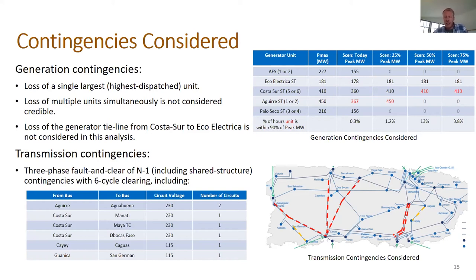All of the contingencies, or actually a subset of the contingencies that we looked at, are summarized in the table on the right, where for each scenario shown in columns going across, you can see the largest conventional units online and what their dispatch was at the time, with the text in red being the megawatt level of dispatch that was evaluated. So some of the units have very high levels of dispatch power production with respect to the total load on the island, meaning it's a relatively severe event that we're looking at.